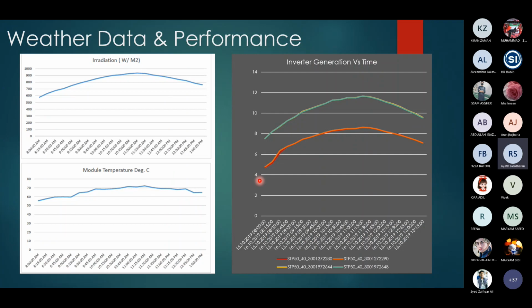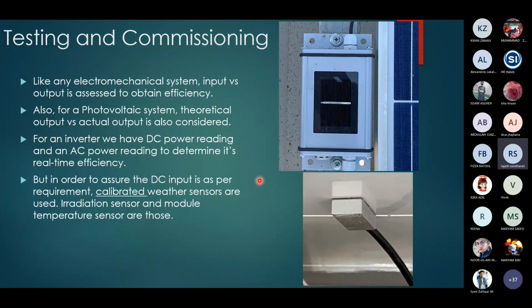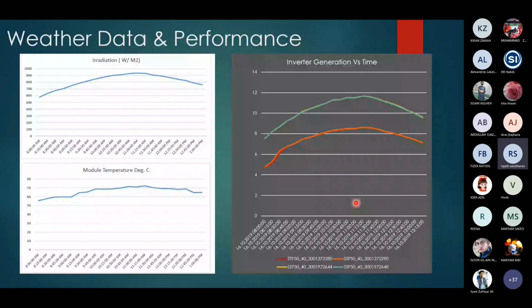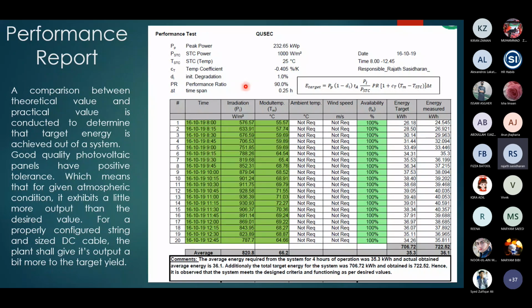These are some reports that we check, like what is the irradiation from the sensor. Here we can see a pyranometer and a module temperature sensor. And using this information, this is the Excel sheet I requested you to make using this equation. I've given this equation already. So what we do is we just copy paste the different irradiation readings taken for about 4 or 5 hours and the corresponding module temperatures. The ambient temperature and wind speed don't really matter. They are not required for the equation, just for comparison's sake.